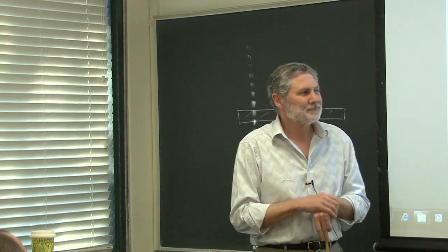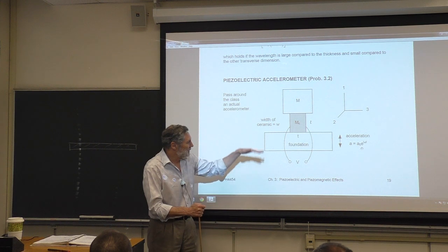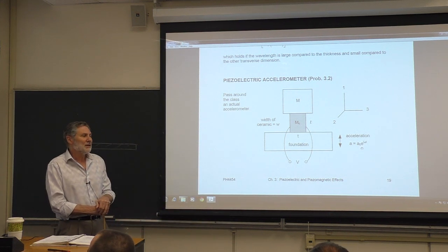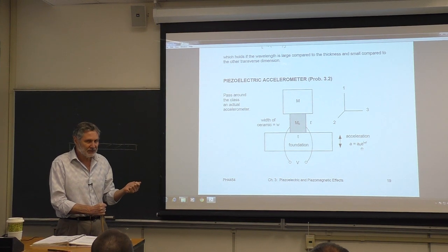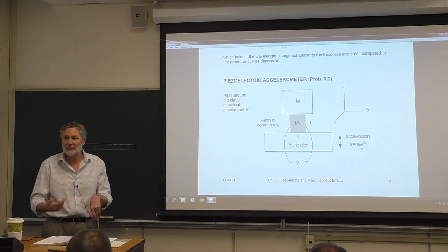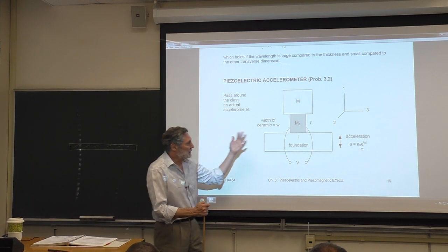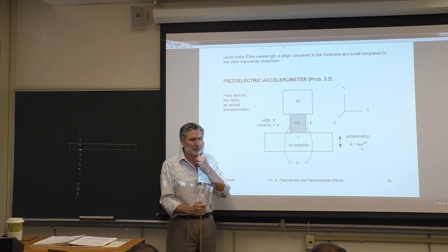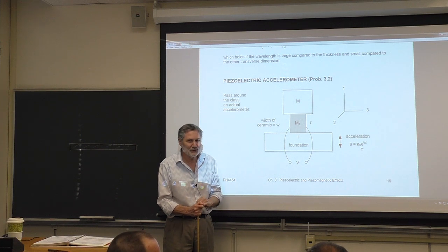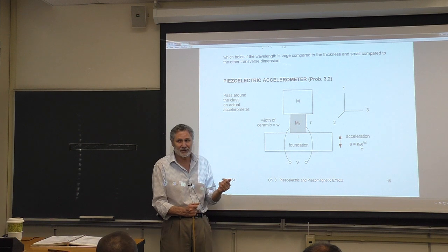So here we go. Here's the idea. There's this word foundation, and this is something that's vibrating, and we want to measure the acceleration. You may be after velocity or displacement, but of course once you have one, you've got the others, because they're related by the frequency. It turns out this is a natural accelerometer. What this transduces is acceleration. It doesn't transduce displacement, it doesn't transduce velocity, it transduces acceleration, and you're going to see why.